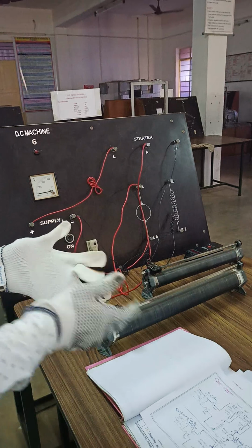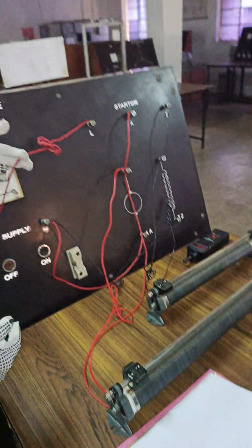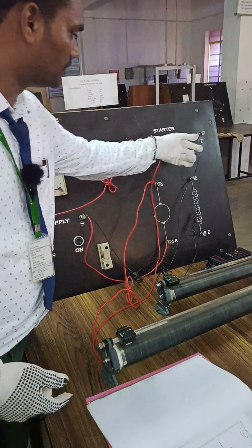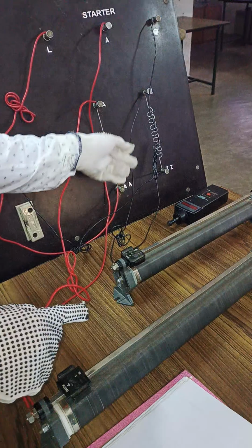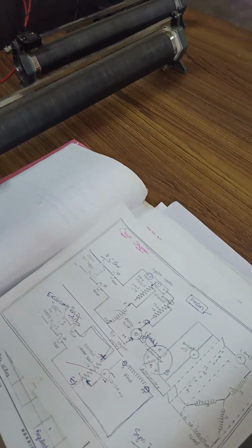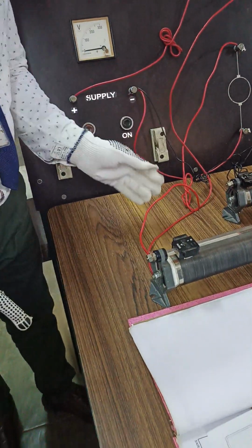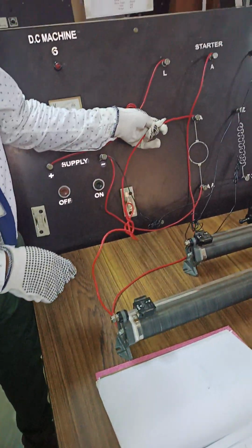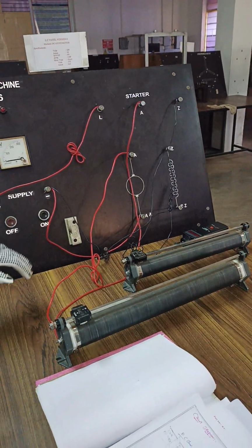So as per the given circuit diagram, this is called the DC shunt motor connection. From positive we are connected to the line, and from Z we are connected to the input of the field rheostat. Output of the field rheostat we are connected to the field winding, and ZZ we are short circuiting as per the circuit of field winding. Field winding current is low, so we are using a thin wire. Now coming to the armature winding. From the armature 3-point starter we are connected to the lower end of the rheostat, and the variable terminal of the rheostat we are connected to the armature winding, and AA we are going to connect to the negative. So this will act like a prime mover.